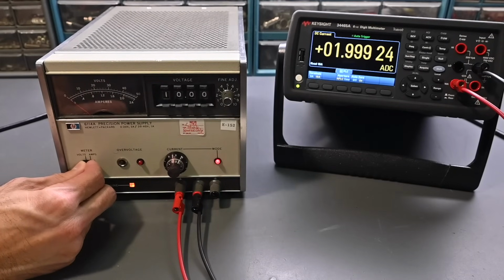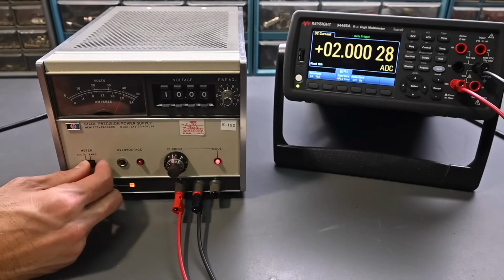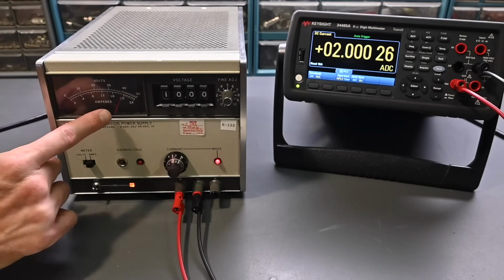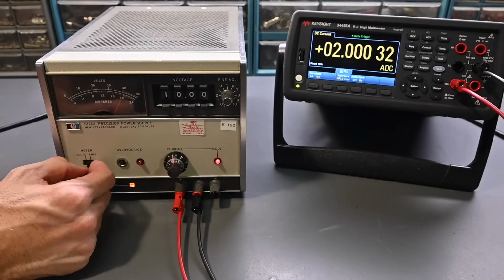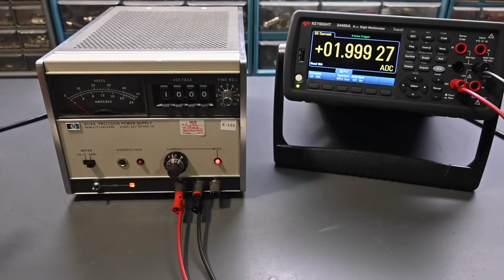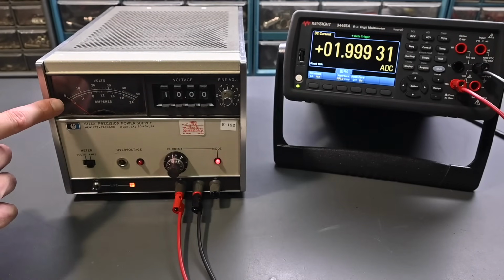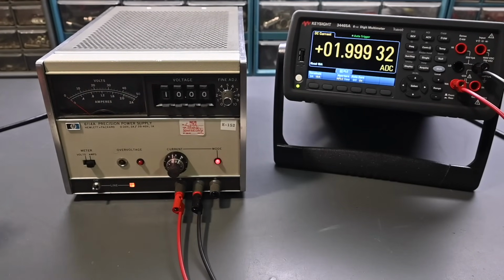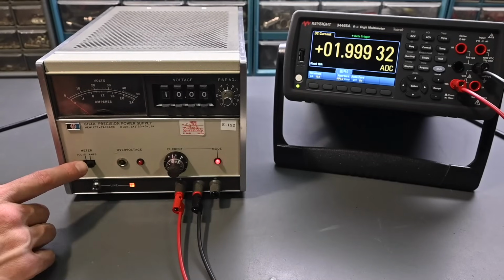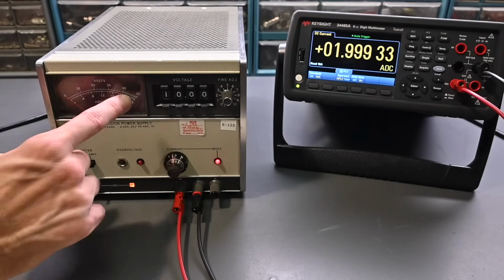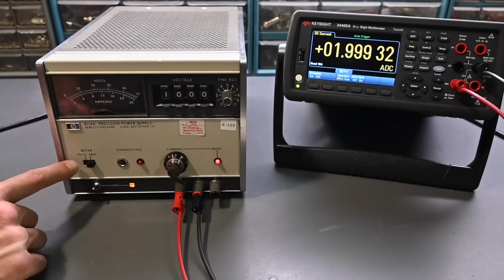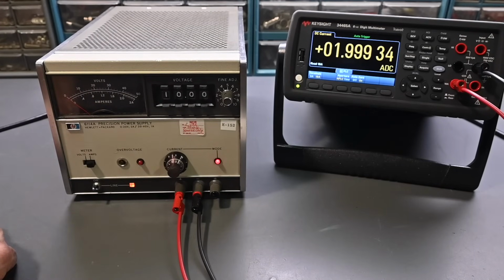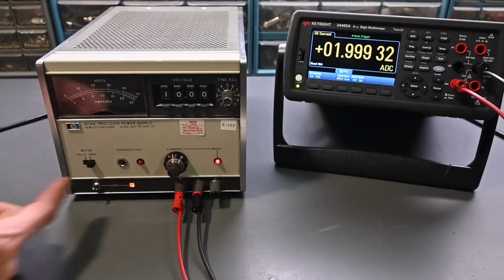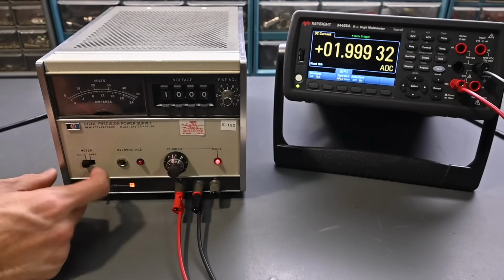This switch actually has improved with use. You can see how it's moving around a little bit there. It wasn't real steady. Okay, there it did it. It's in amps and it's not moving at all now. And that's what it was doing when I first powered the power supply. It basically wouldn't work at all for indicating amperage. So there's definitely an issue going on with this switch. It needs to be cleaned up, I would imagine, unless there's a wire that has come loose or something like that. But it's probably just that the switch contacts have become dirty. So again, some cleaning in there is probably necessary.